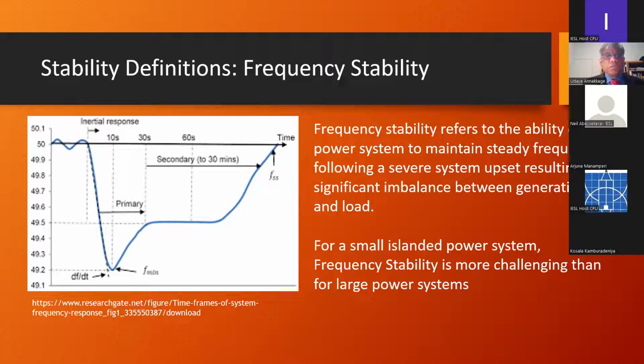So the response of the system frequency has, as you can see, 3 overlapping periods. First period is the inertial response, then the primary frequency control response, that's the governor response, and the secondary frequency control response, that's the response of the automatic generation controllers, essentially giving integral feedback, or it could even be a system operator in a control room, system control center, adjusting the power generation set points of generators to bring the frequency back to the nominal frequency of 50 Hertz.